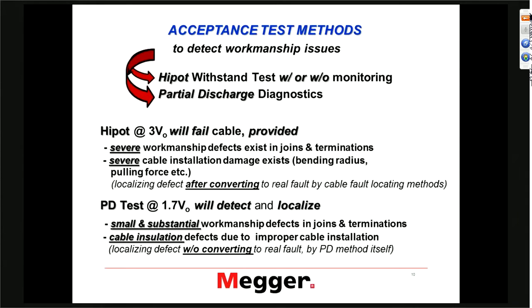So it is a fair assumption to say that a partial discharge test is a very good test to find out whether you have issues in splices and terminations in terms of acceptance testing. There are different ways to monitor a hipot test. You can use partial discharge levels to monitor a hipot test. You can use Tan Delta to monitor a hipot test. And you can also use leakage current.